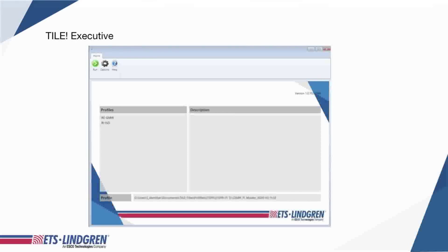We offer the TILE Executive. The TILE Executive is a software shell that allows an operator to select a profile — profiles can be added by an engineer. You can actually set security protocols on the computer so that an operator-level person can only select one of the profiles in the executive. You can keep your golden master profiles available here and force the test technician to use those.